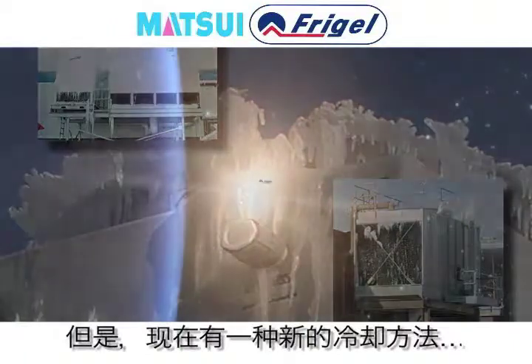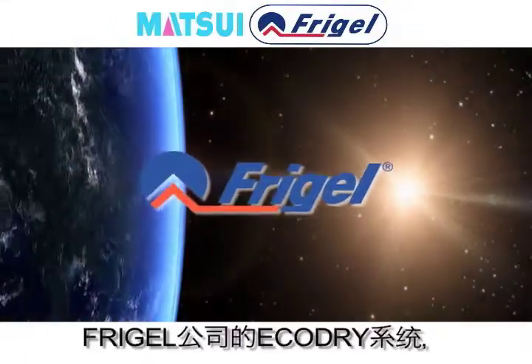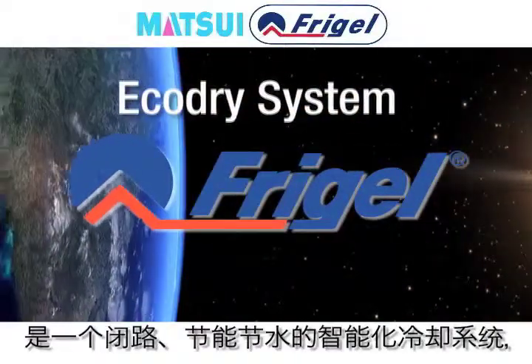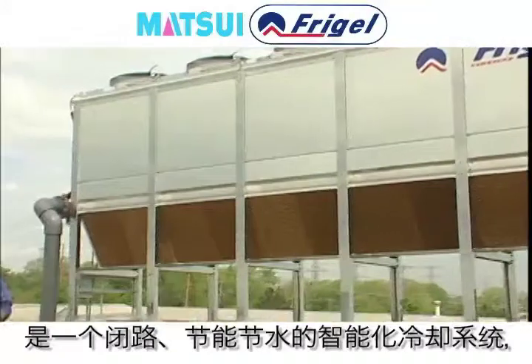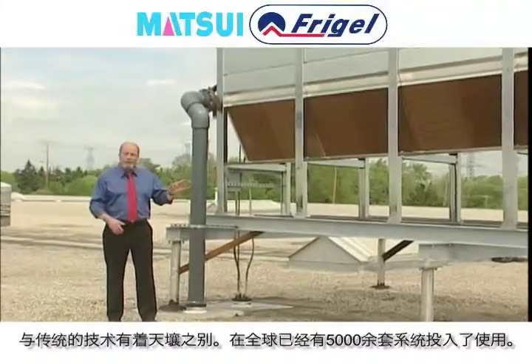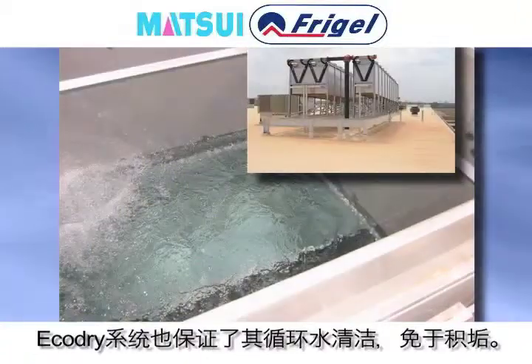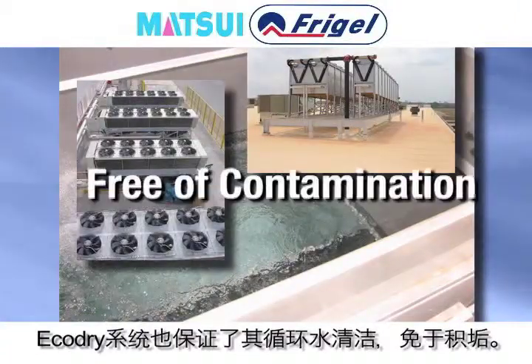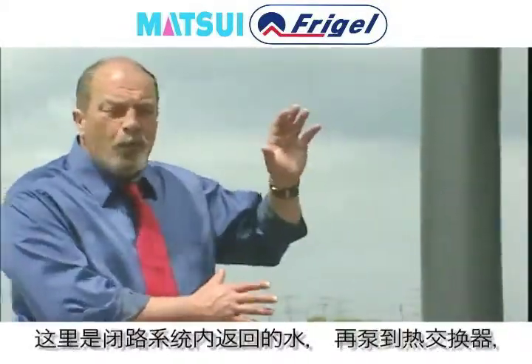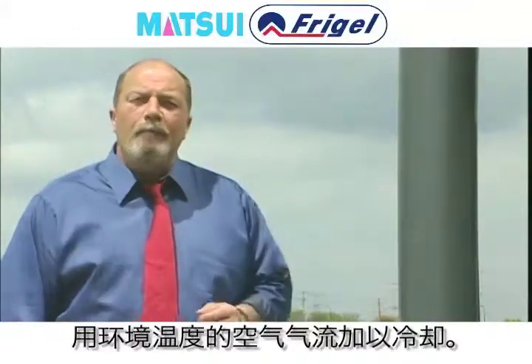But there is a new day in process cooling. Right now, in thousands of global installations, the Ecodry system by Frigel is making a profound difference. Its closed-loop intelligent cooling system is designed to use energy and water wisely. The Ecodry system also keeps water clean and free of contamination. Right here is where the closed-loop water is returned, pumped into a heat exchanger, and cooled with ambient airflow.